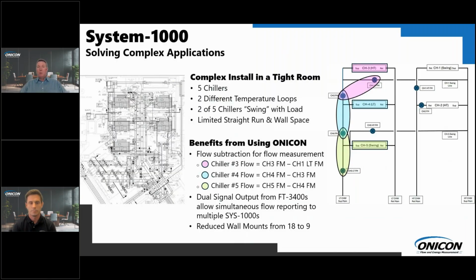Since there was no room for flow meters in the risers from the chillers, we placed flow meters in the headers of all the mains, and we're using flow subtraction so that we can take measurements off the main and subtract out before and after chillers, determine how much flow is actually going through the chillers. So if you look at the colors on the diagram, you see the pink oval that's circling 2 flow meters. We're using flow subtraction there to identify the actual flow going through the pink square that is chiller number 3. We've then repeated that down the line in the header with the teal chiller number 4 and the yellow chiller number 5. We're using the flow subtraction features of the System 1000 to help this engineer solve the problem with this complex install.